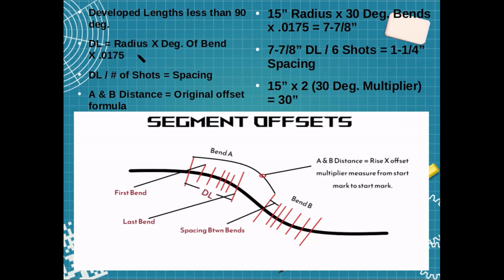Let's say you already have the radius and you're going to fill in the actual formula. For this example: three-quarter EMT, radius is 15 inches, offset is for 30-degree bends, and offset height is 15 inches. Filling in the formula — radius 15 inches, degree of bend 30 — it's radius times degree of bend times 0.0175. Remember that decimal value, 0.0175.